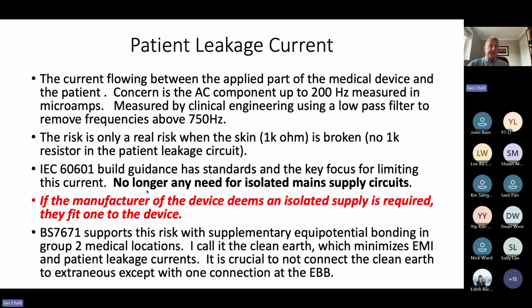And this risk of patient leakage current goes up significantly when they're sticking things into the human body, i.e. breaking the skin, because the touch current that you're aware of is limited by the skin, which is 1 kiloohm. But when you start connecting to the vascular system, you remove that 1 kiloohm circuit. So all the values change. And that's when microamps become a concern.